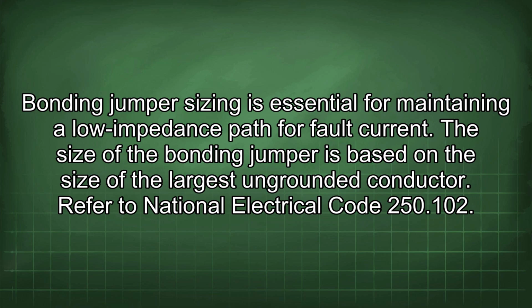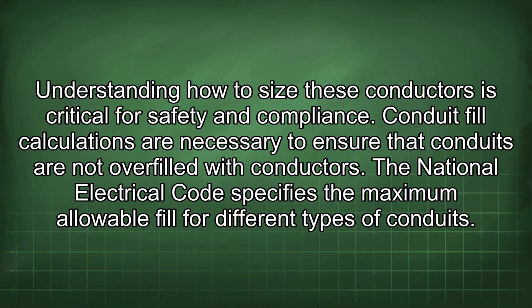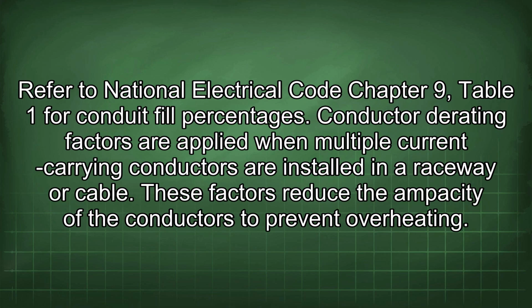Refer to National Electrical Code 250.102. Understanding how to size these conductors is critical for safety and compliance. Conduit fill calculations are necessary to ensure that conduits are not overfilled with conductors. The National Electrical Code specifies the maximum allowable fill for different types of conduits. Refer to National Electrical Code Chapter 9, Table 1 for conduit fill percentages.